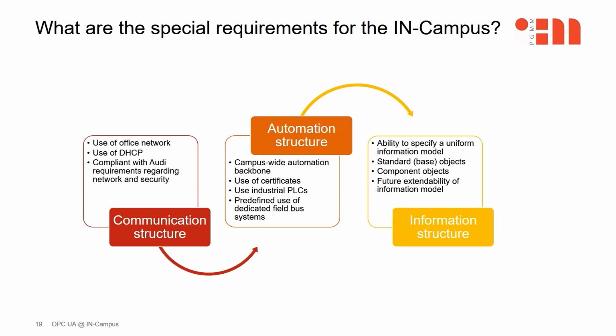Now to the information structure. For uniform exchange of information, it must be possible to develop an information model that meets both today's needs and openness for expansion to meet future needs. For this task, a variety of object types must be provided. These are, on the one hand, standard objects such as digital and analog inputs and outputs, and on the other hand, component objects for acquisition of devices, plants, and systems. Component objects can be, for example, pumps, valves, chillers, heat pumps, or even buildings.